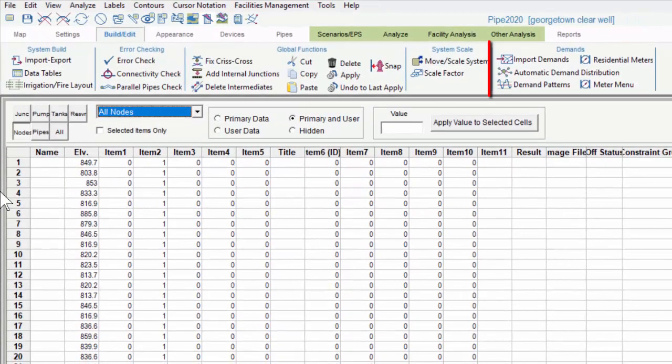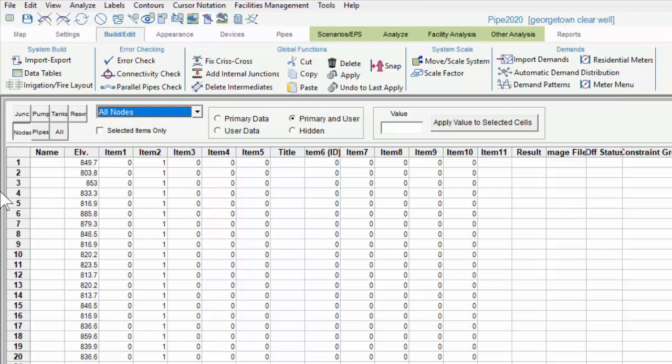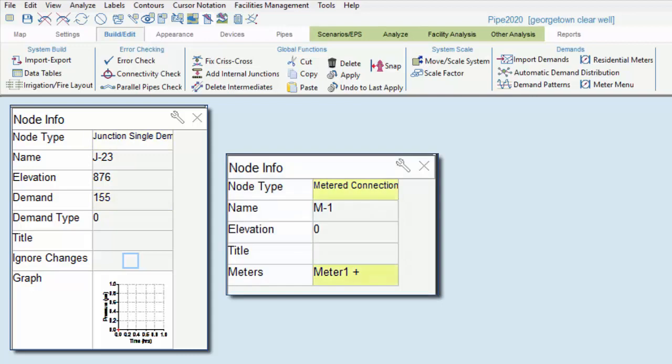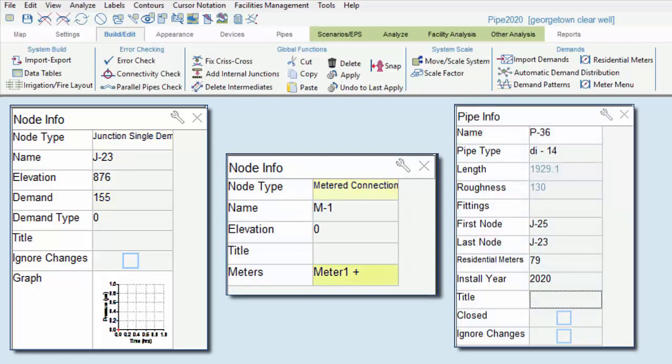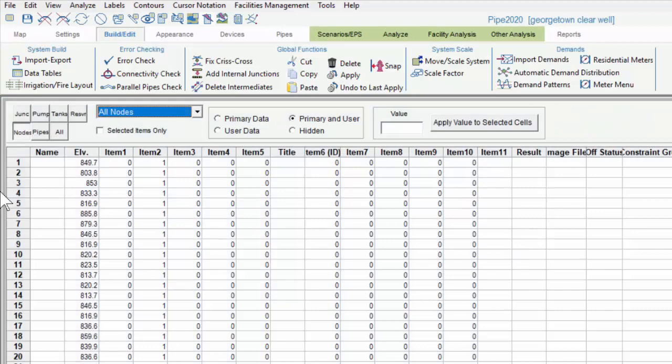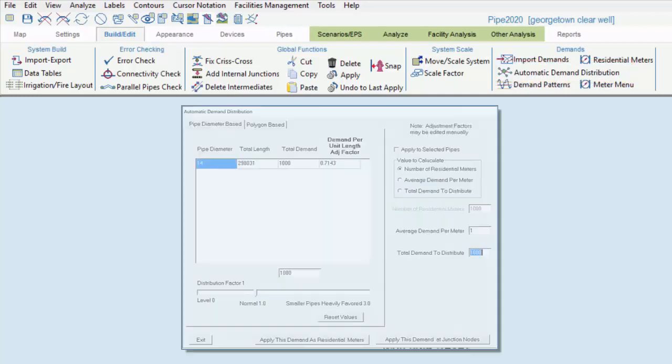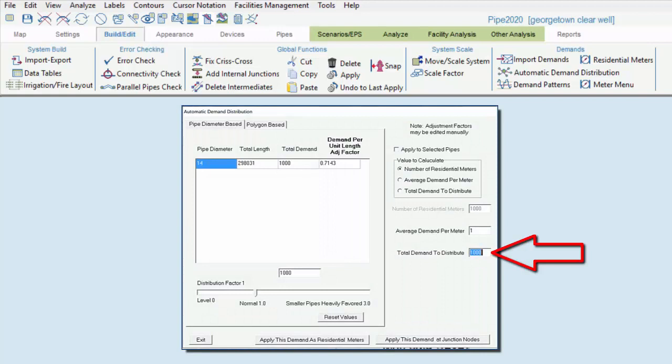Demands can be created and edited here. In KYPipe, some demands are associated with nodes, such as junction demands and metered connections, and some are associated with pipes, such as residential meters. So, while those functions are also available under their respective menus, demand inputs are also available here because demands are often applied and edited globally throughout the model. For instance, KYPipe's automatic demand distribution feature allows us to enter the total demands for an area, such as a city, and the software will distribute the demands to different pipes based on factors such as pipe diameter.